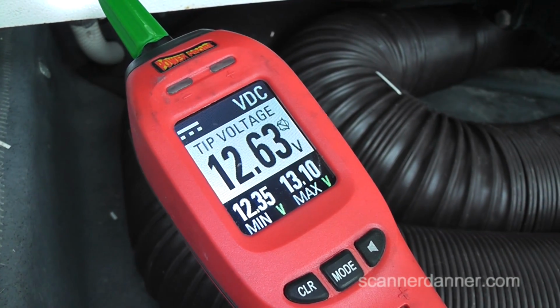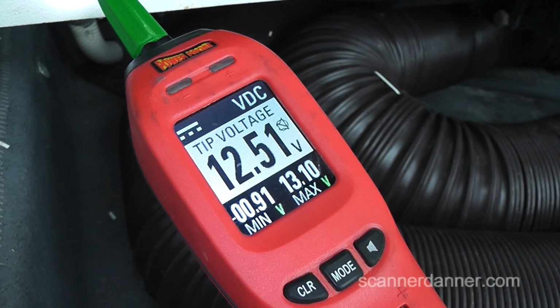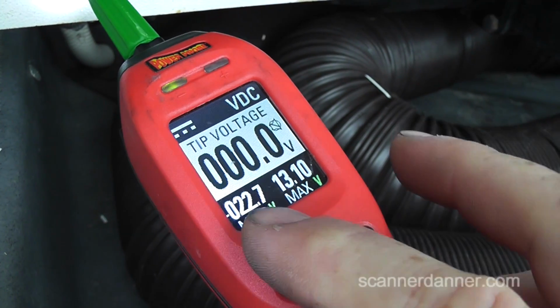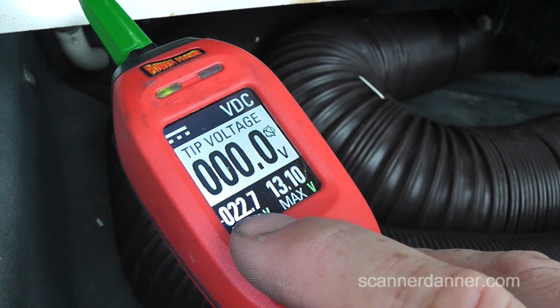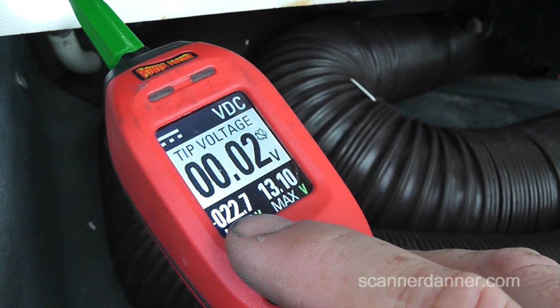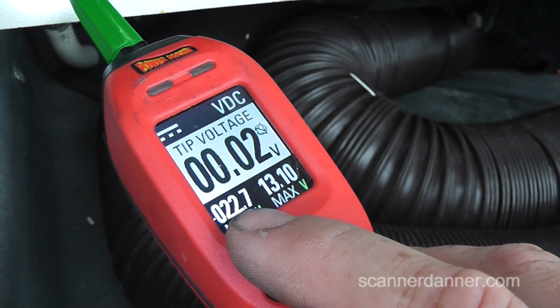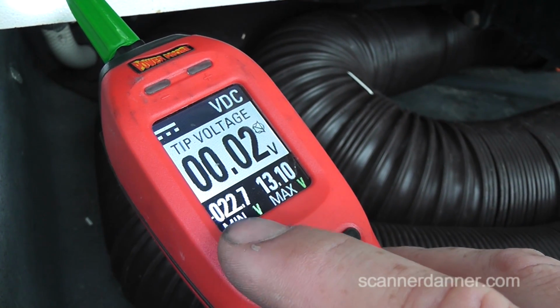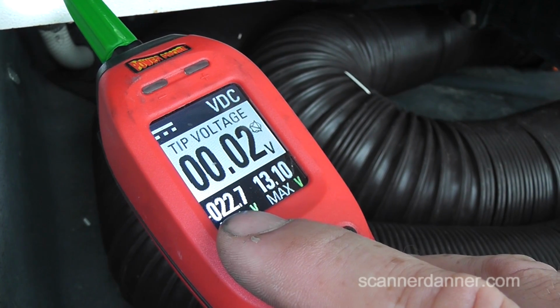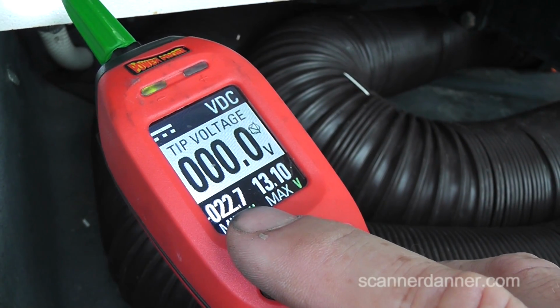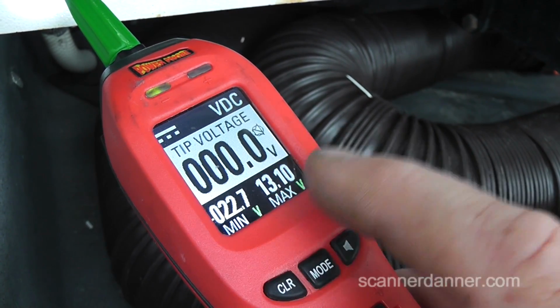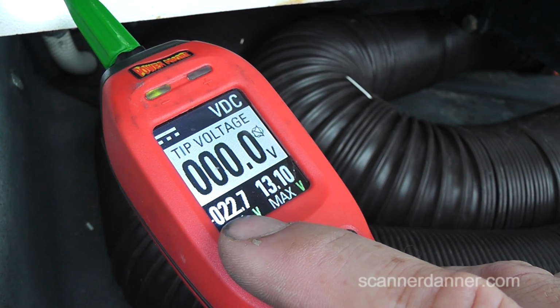All right, now go ahead and let off, Beau. You see this side dropping down to 0 volts, and we have a minus 22 in that case, and that's just from the motor turning on and off. You're going to have electric surges, you're going to have voltage spikes, okay. It is normal when you're troubleshooting this on the feed side to see at times this voltage drop to 0.